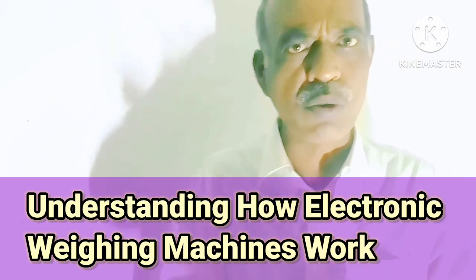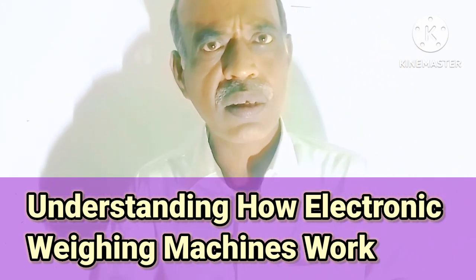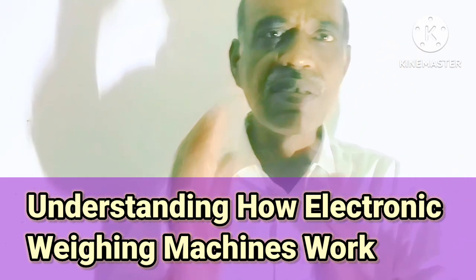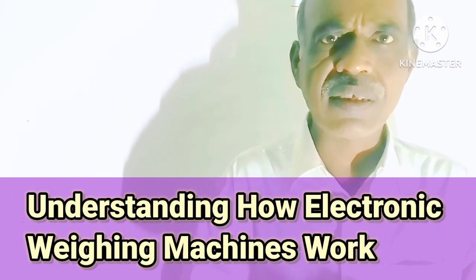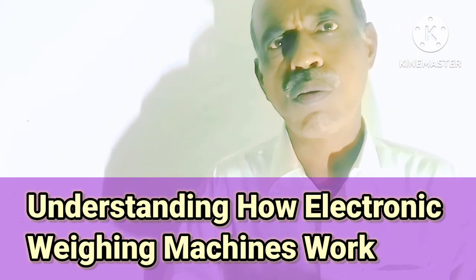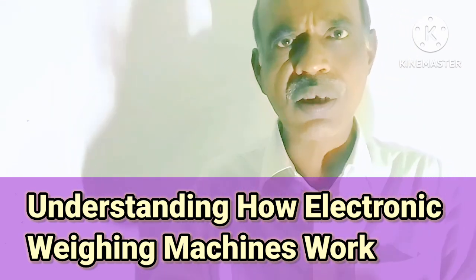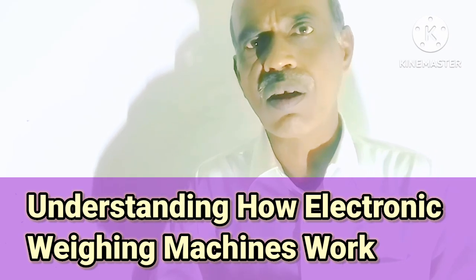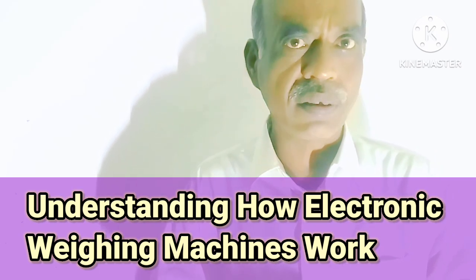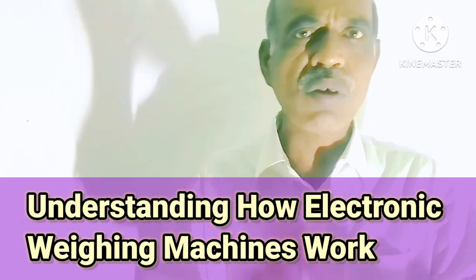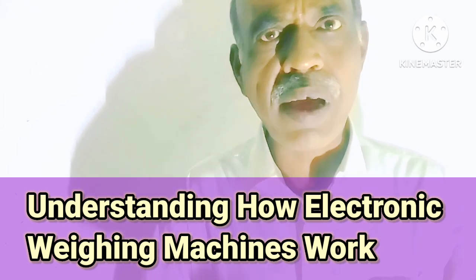You know the function of the Wheatstone bridge. By measuring the resistance of the strain gauges, it is known what load was applied. But more units are there, such as the microprocessor unit.